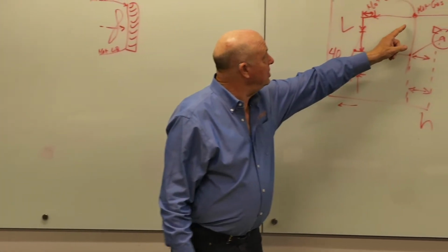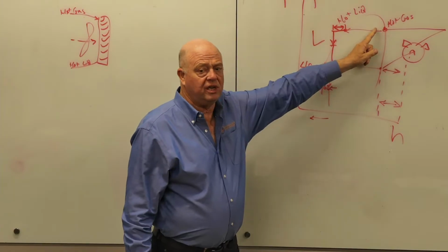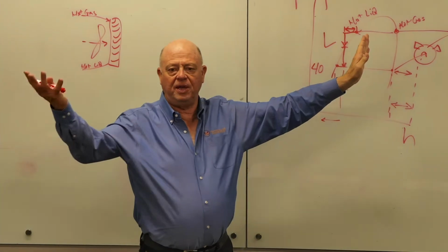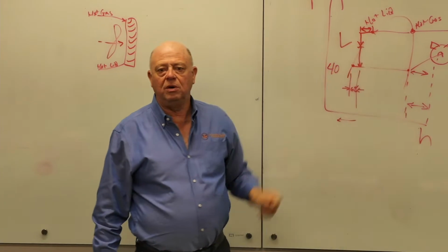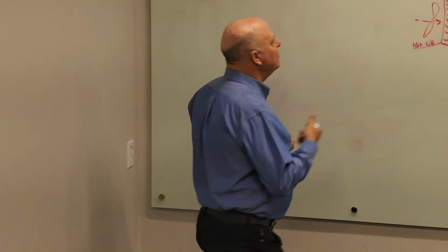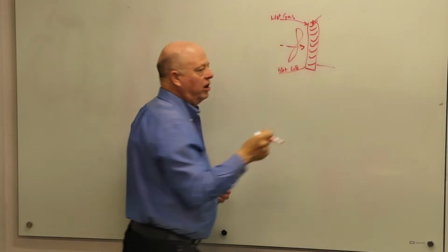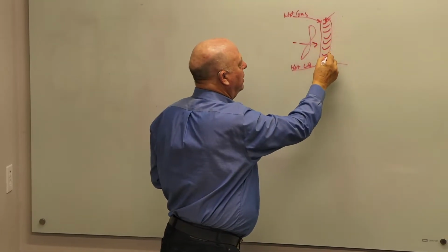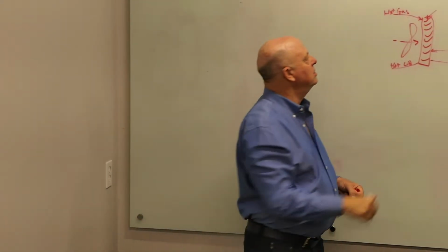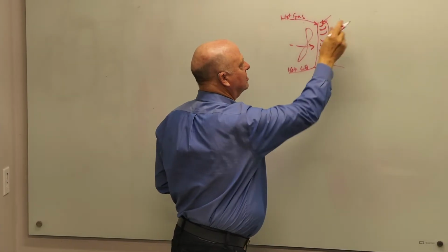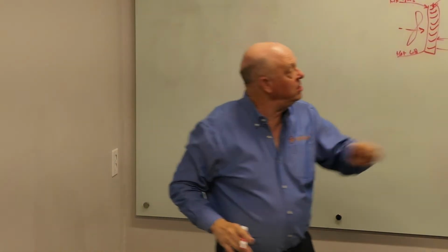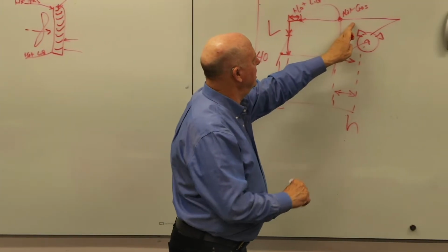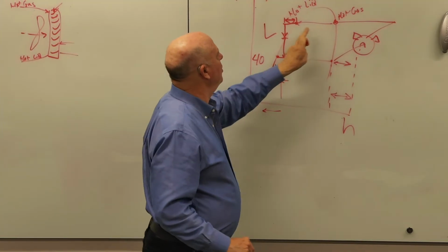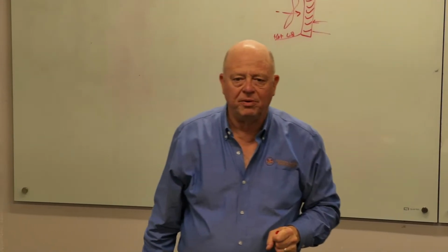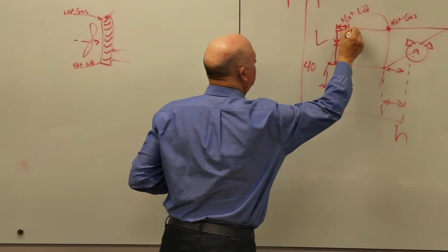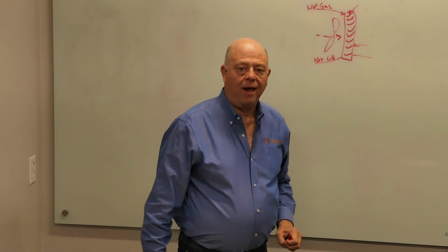And that's exactly the process that you're seeing here, right? We come through, the hot gas hits the condenser. Initially, it's 100% hot gas. But as it condenses, it's giving up heat. And as we move across here, eventually we get to liquid, and the liquid's cooler. If I took my laser thermometer, I would expect that this would be at whatever the discharge temperature of the gas was. But once we start to condense, and that's probably the second tube, this is the first pass, all gas probably, just starting to condense. Once we're fully within the dome, because initially that first pass is probably this hot gas up here, then we're within the dome, and your laser thermometer will not change temperatures. Right? We will have the same temperature from the time we hit here till the time we hit there. And it will stay the same.